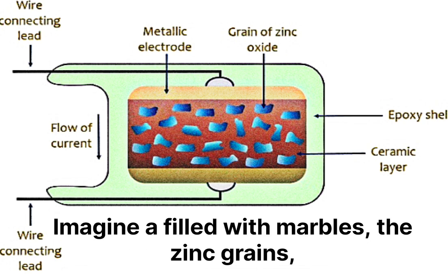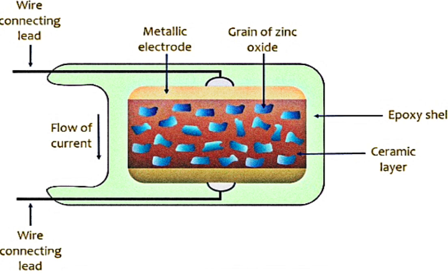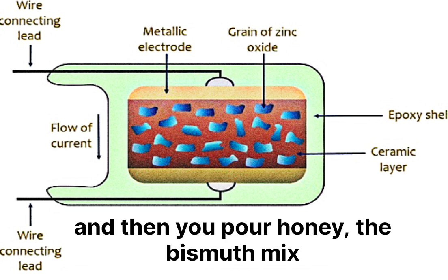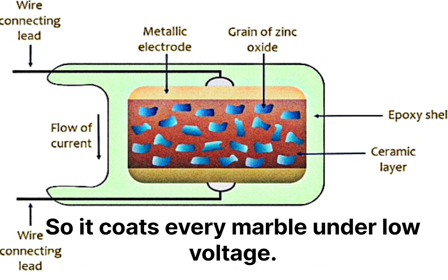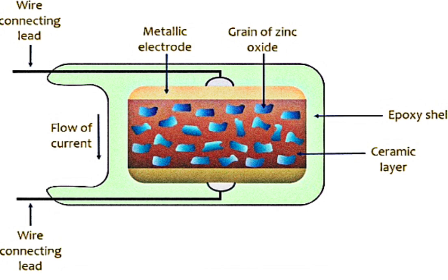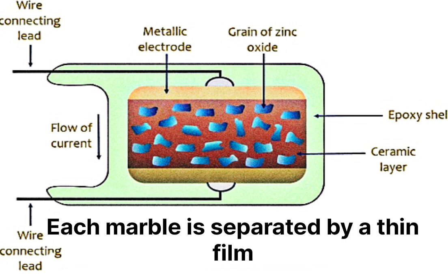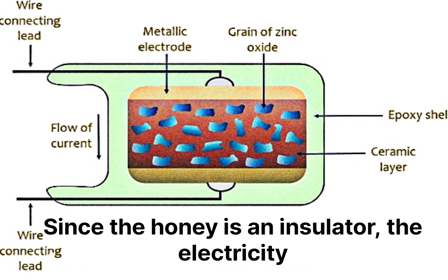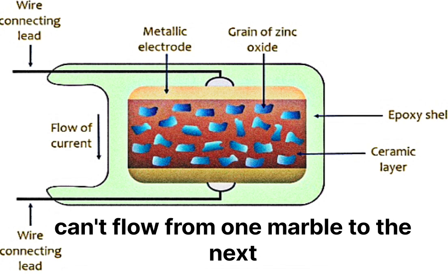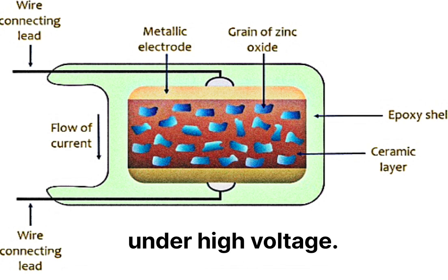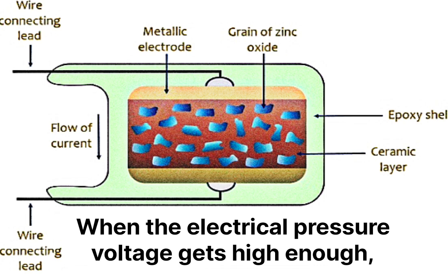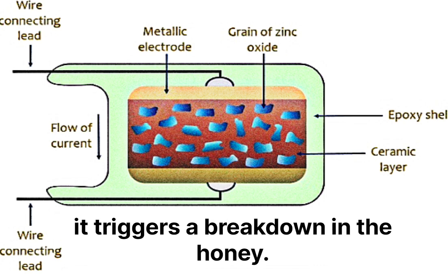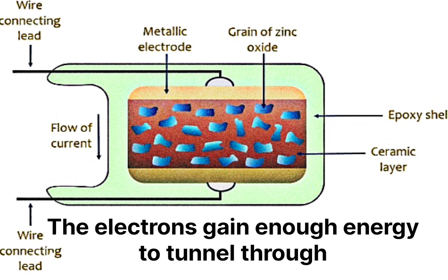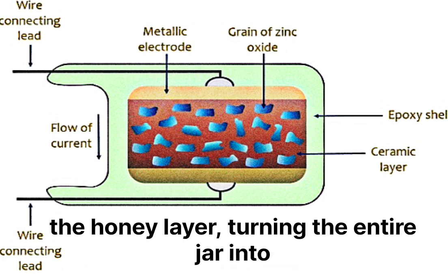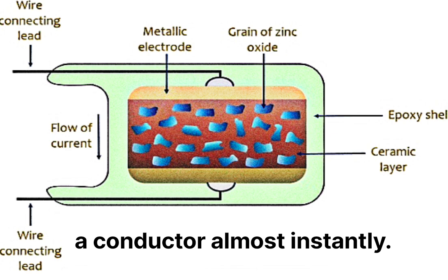How the balls behave. Imagine a jar filled with marbles, the zinc grains, and then you pour honey, the bismuth mix, into the jar so it coats every marble. Under low voltage, each marble is separated by a thin film of honey. Since the honey is an insulator, the electricity can't flow from one marble to the next. Under high voltage, when the electrical pressure, voltage, gets high enough, it triggers a breakdown in the honey. The electrons gain enough energy to tunnel through the honey layer, turning the entire jar into a conductor almost instantly.